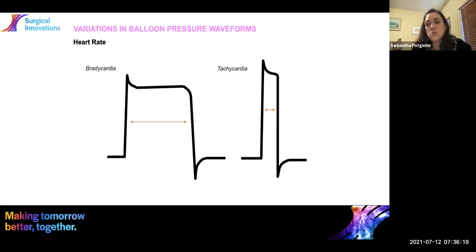So typically your pump console is going to alarm, and it's going to tell you that it isn't achieving the augmented pressure that you've asked it to achieve. So it automatically can see that it isn't delivering what it needs to. It also isn't fully inflating, so you've got a threat of blood clot formation on the surface of the balloon catheter itself, because the catheter has folds in it now because it can't completely inflate. So in a tachycardia, we need to address what's going on with the patient, because we do need the balloon to fully inflate and to fully deflate so that it doesn't affect the timing.